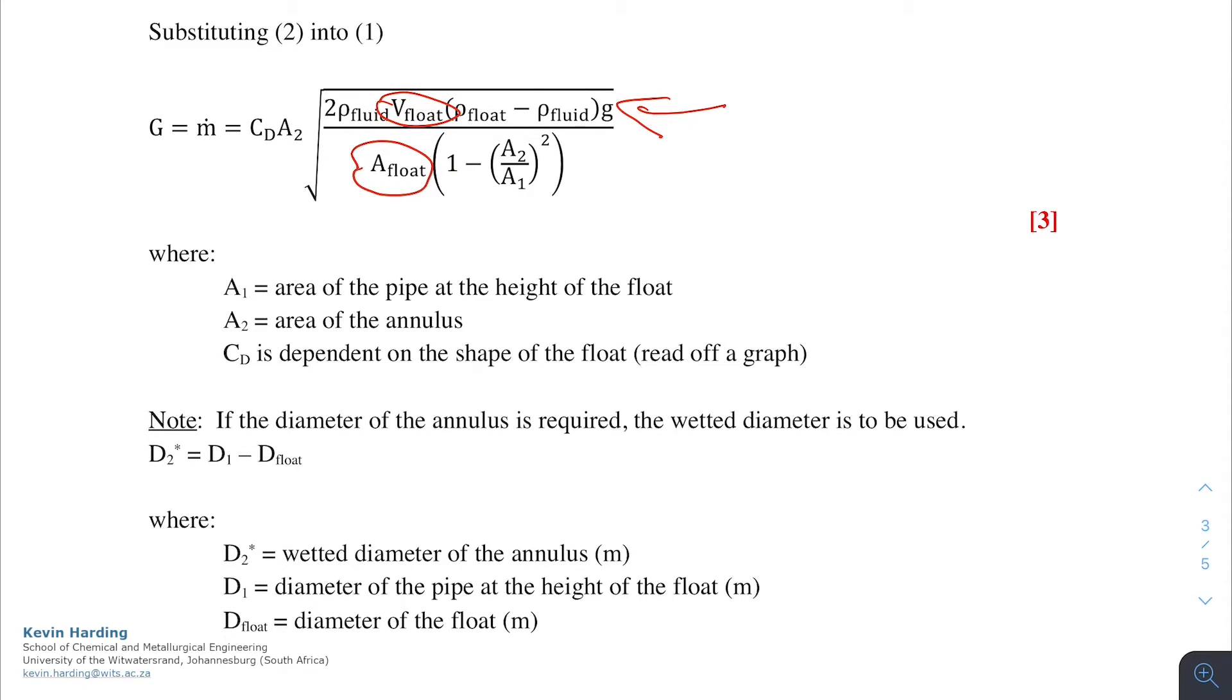One of the differences here is that when we are looking at area A2, which was the area of the annulus, please note that we need to use the wetted diameter to find that area, where the wetted diameter is the difference between diameter D1, the total diameter, and the diameter of the float.